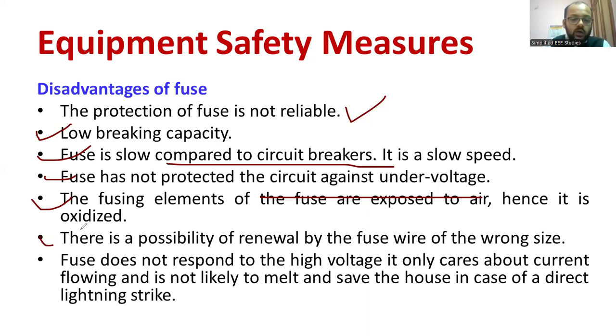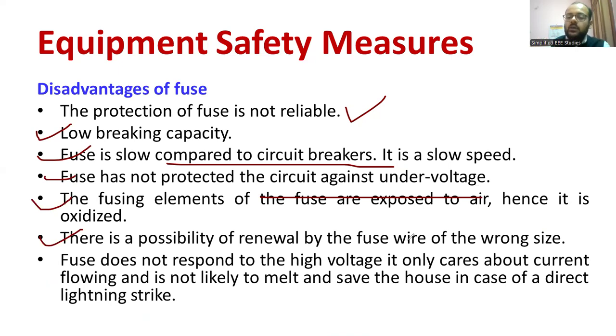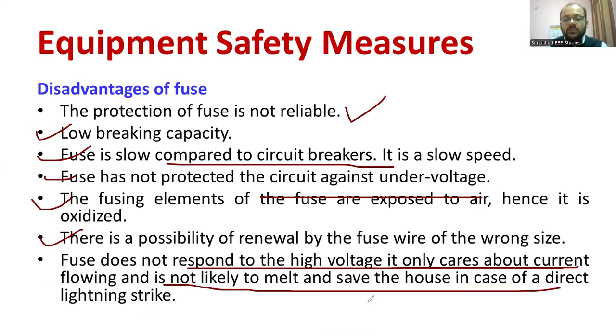There is a possibility of renewing the fuse wire with the wrong size. Sometimes people use thick wire without checking the specification, and the purpose will not be served. If thick wire is used, it will never melt even when fault current passes through it. The fuse does not respond to high voltage — it only monitors current. It cannot protect against cases like a direct lightning strike.